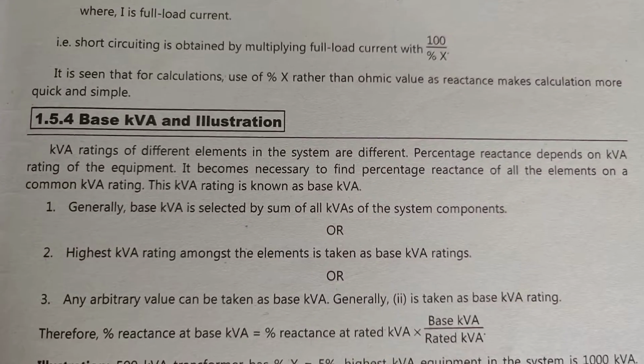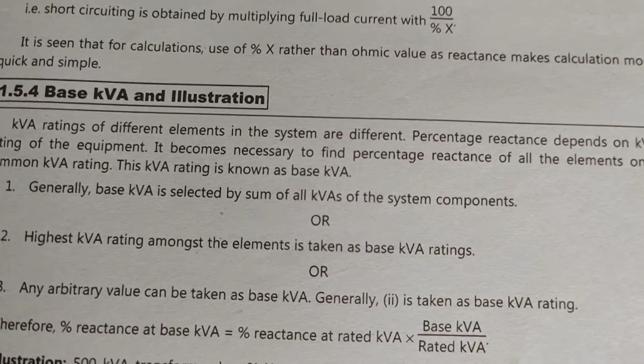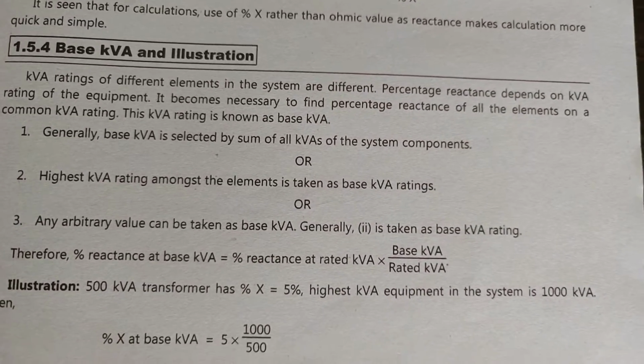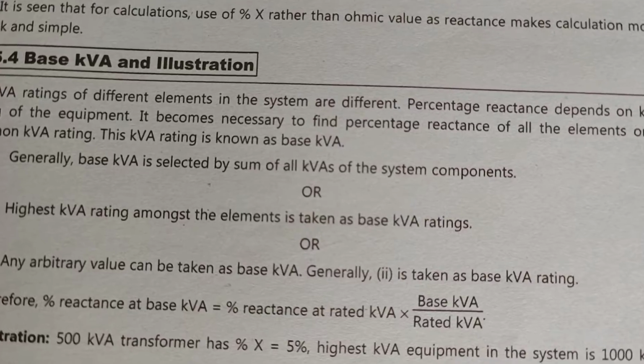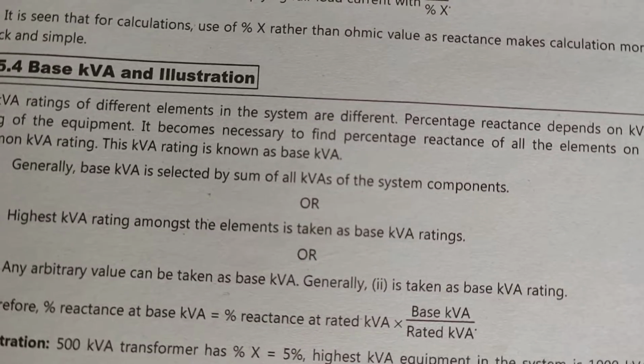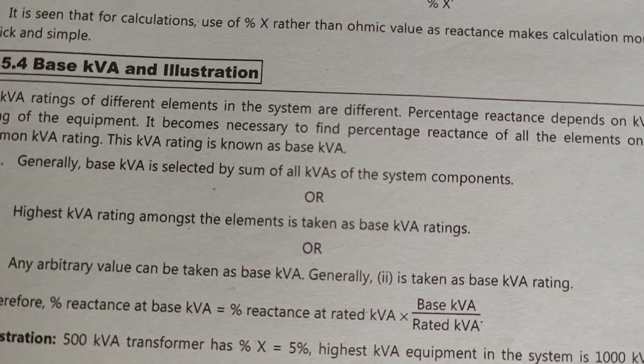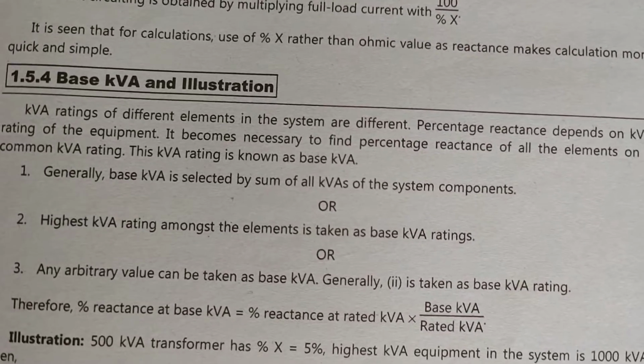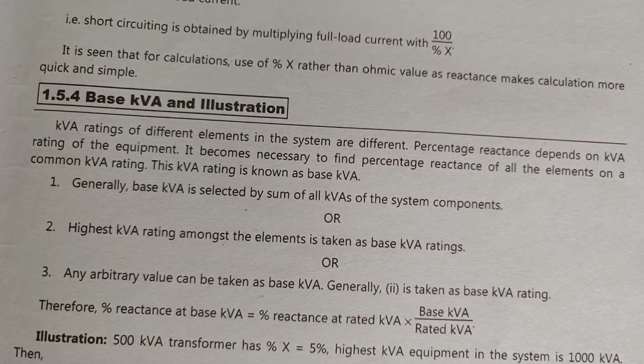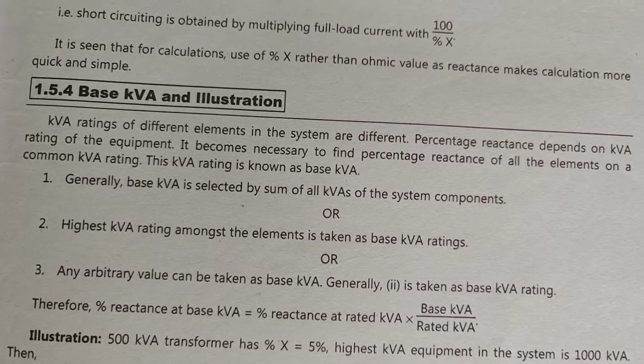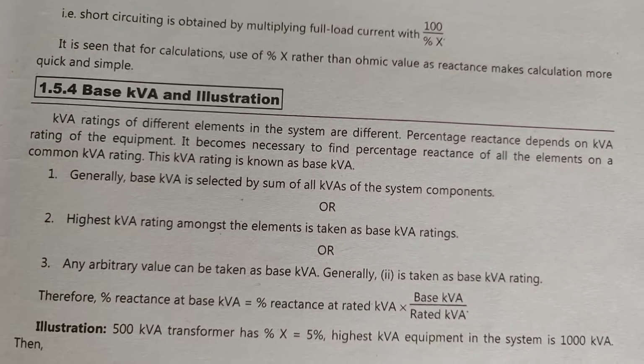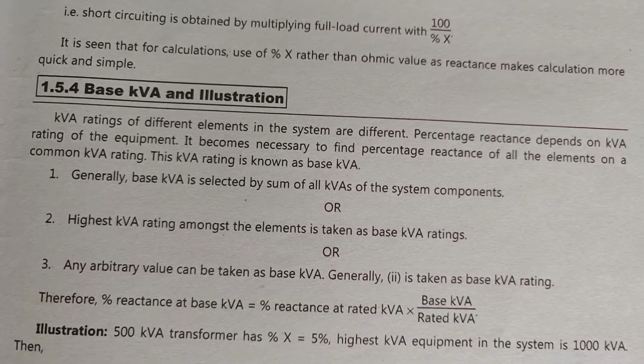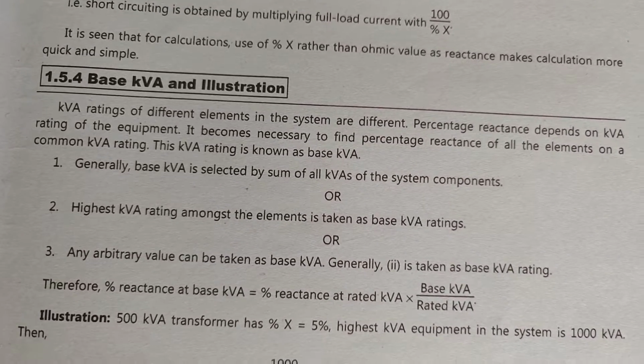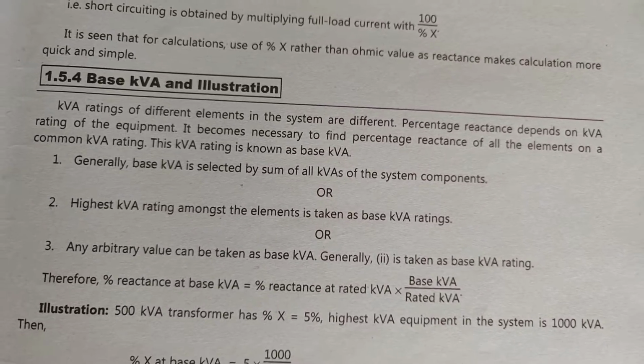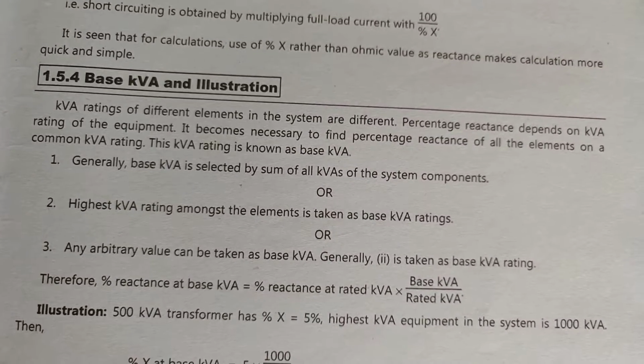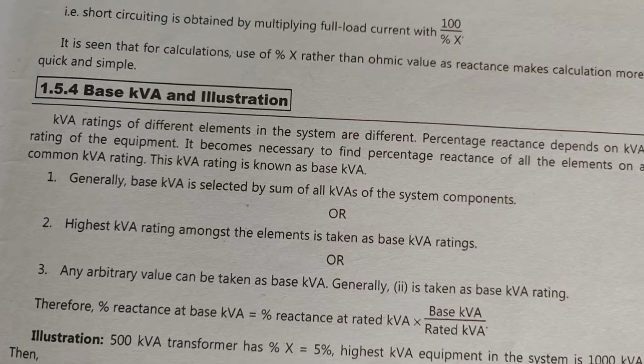Here, generally, base kVA is selected as the sum of all kVAs of the system components, or the highest kVA rating amongst the elements is taken as base kVA rating, or any arbitrary value can be taken as base kVA. Therefore, percent reactance at base kVA equals percent reactance at rated kVA into base kVA upon rated kVA.